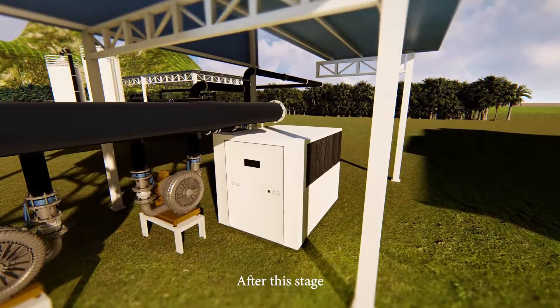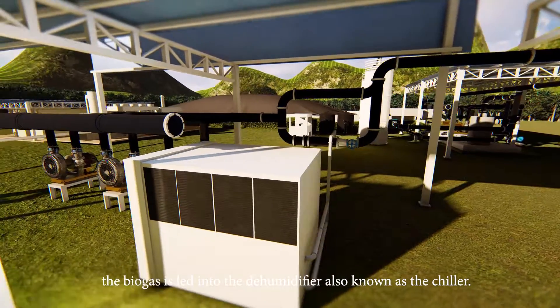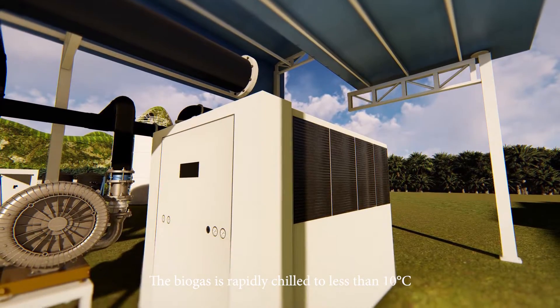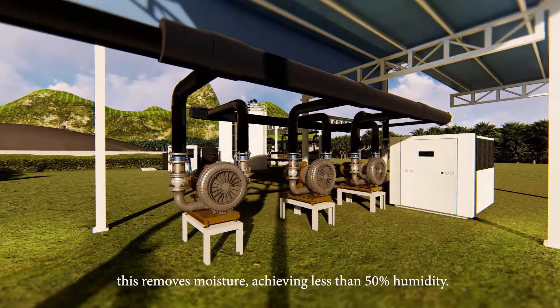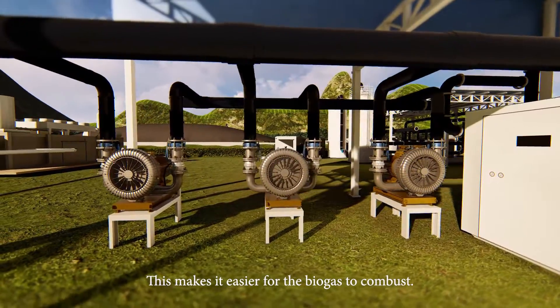After this stage, the biogas is led into the dehumidifier, also known as the chiller. The biogas is rapidly chilled to less than 10 degrees Celsius, removing moisture and achieving less than 50% humidity. This makes it easier for the biogas to combust.